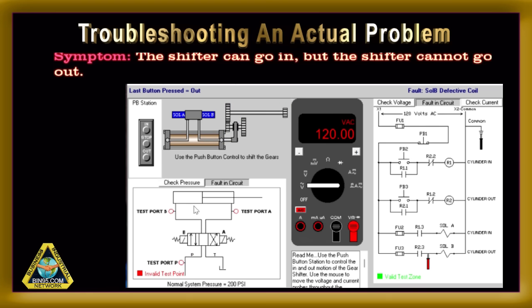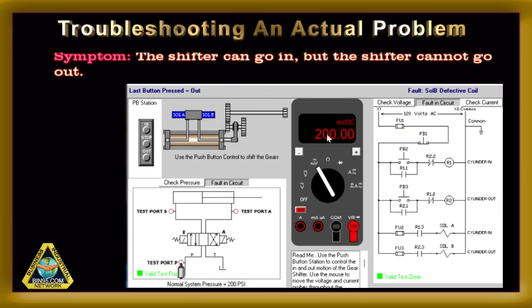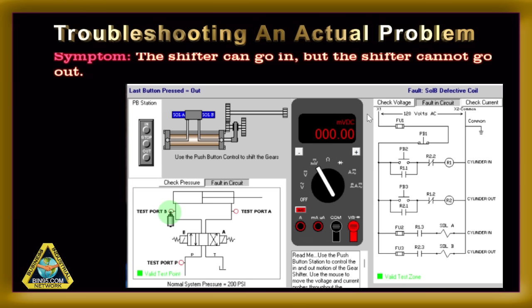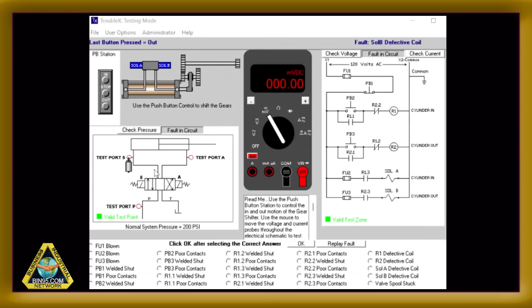This particular cause of the symptom was easy to trace back and determine in no time. We confirm the cause is solenoid B by checking the incoming pressure, be it air or hydraulic. Pressure is good at the input to port B. Then, while solenoid B is energized, we check the output from port B. That measurement indicates zero pressure, confirming solenoid B is defective. In the TroubleX simulation software, the student would select solenoid B defective coil as the correct fault for this problem.